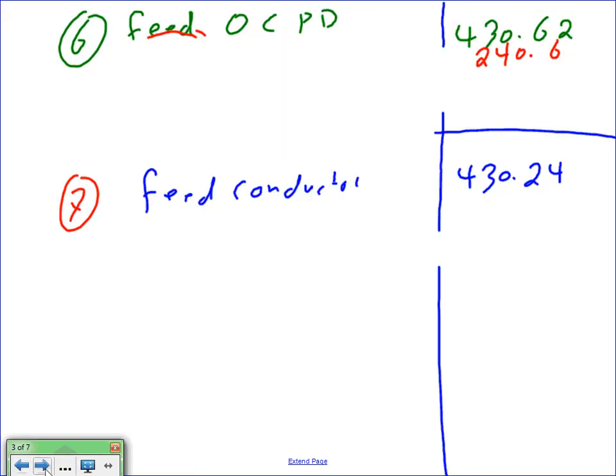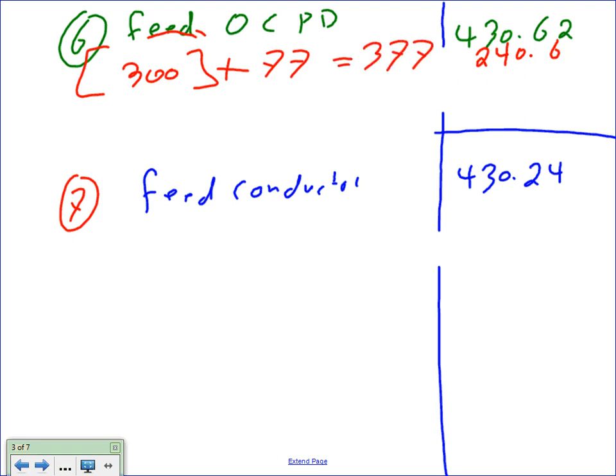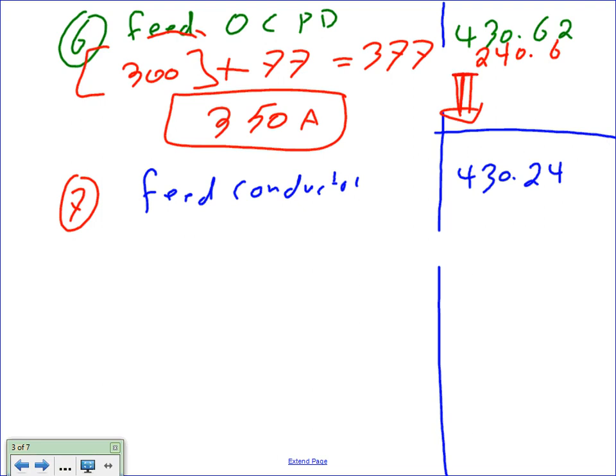The second thing, guys, I need the feeder overcurrent protection device. The feeder overcurrent protection device, Chris, you take the 300 amp largest, fattest fuse, add to it 77 amps, you end up with 377. And if it's not a standard, you have to go down to 350 amps. So your overcurrent protection device has to be this amount or lower, the maximum overcurrent protection device.